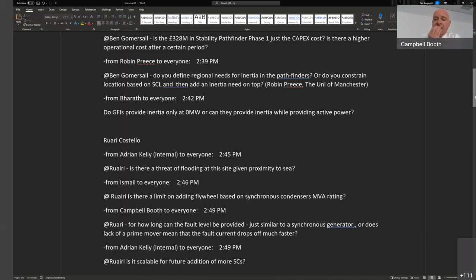Probably similar to what machines would generate when normally operating in motor mode. There was another one, the damper bars. That's a good point. We used to use damper bars in a smaller machine. I don't think you can use them in a synchronous condenser because you already have a large rotor there. Adding damper bars is not good for the design. So we'll start the motor with a frequency converter, take it to synchronous speed, and then synchronize it with the grid. Then you keep the motor or synchronous compensator running throughout, 24/7, 365 days, apart from scheduled maintenance.